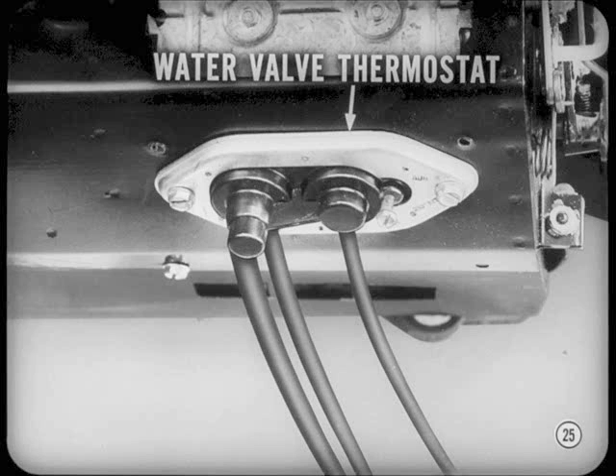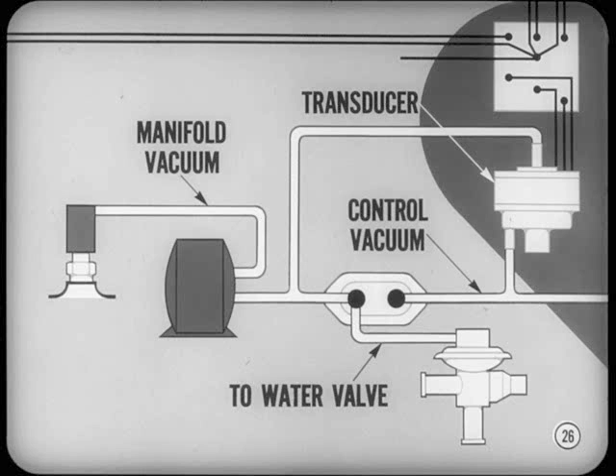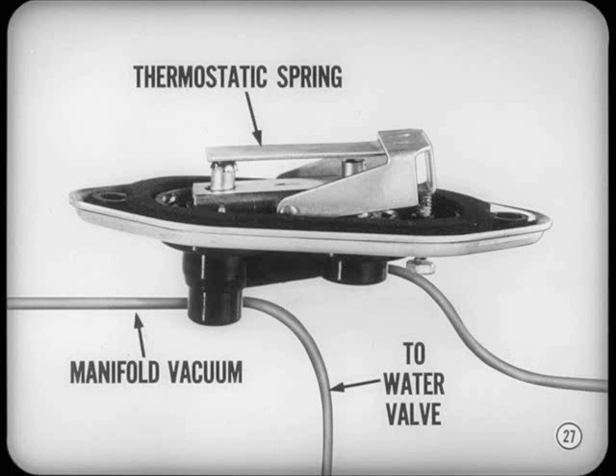Instead, a water valve thermostat located in the discharge airstream modulates manifold vacuum to minimize temperature fluctuations and maintain a fairly constant discharge air temperature in spite of variations in engine coolant pressure and temperature. There are no water connections at the thermostat, only vacuum line connections. One vacuum line is connected to manifold vacuum, one to the water valve diaphragm, and one is a control vacuum line from the transducer. A thermostatic spring in the water valve thermostat reacts to changes in discharge air temperature to regulate manifold vacuum. For example, as the discharge air warms up, the thermostatic spring tends to reduce the vacuum to the water valve. This in turn reduces water flow to the heater core.